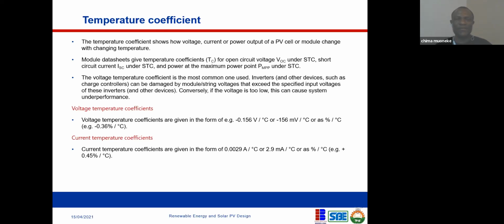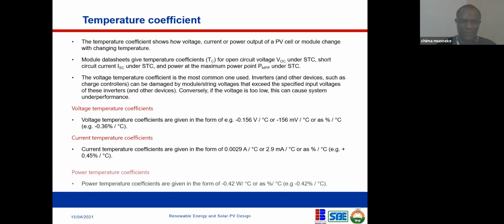So if we're going to do a mathematical example, say you want to install a solar PV in a location and you measure the temperature, and the temperature, for example, is 36. But of course, you know the standard test condition is 25. So you know the difference. For every degree rise in temperature, your voltage is going to drop. So it helps you to calculate the amount of losses you're going to have because of that high temperature. That's what this helps us to achieve.